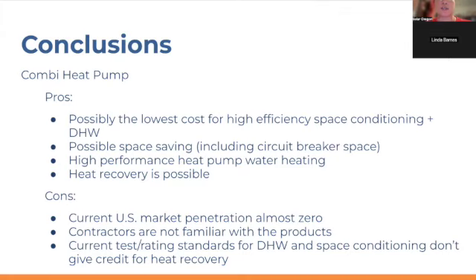And the test and rating standards for domestic hot water and space conditioning neither give credit for heat recovery, because they're separate tests, so they never expect a system that combines the two and can do heat recovery. So if you buy a system that's capable of heat recovery, you're not going to see that benefit reflected in either the domestic hot water ratings or the space conditioning ratings.